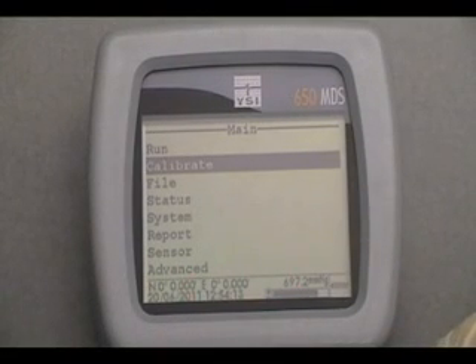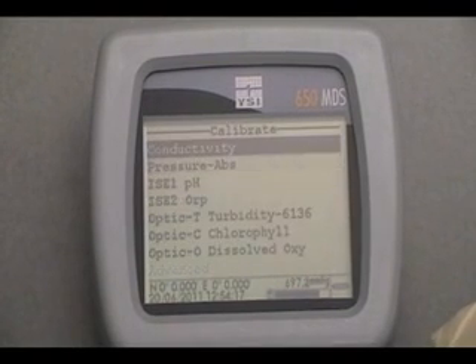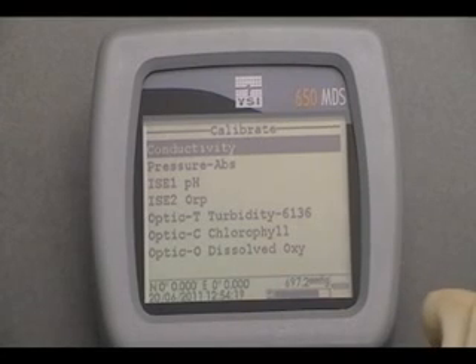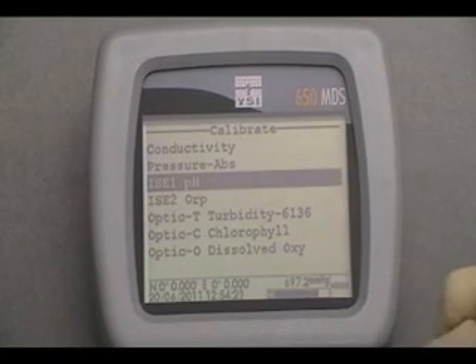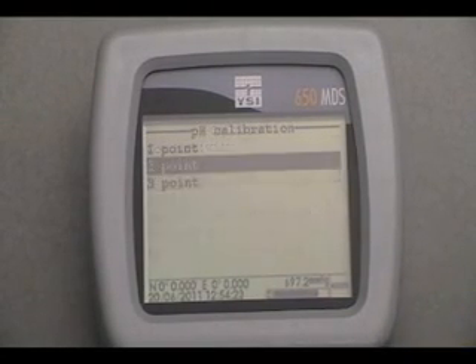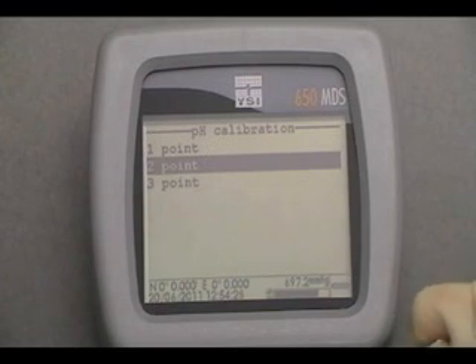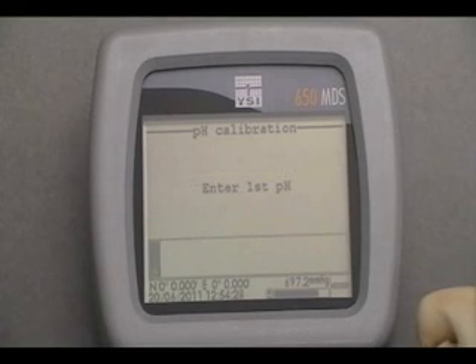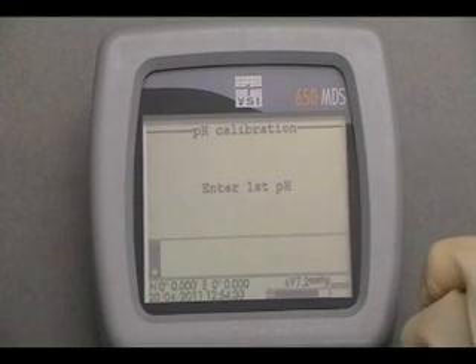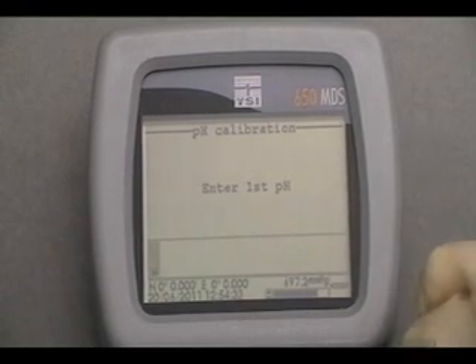Step 4. From the sonde menu, select Calibrate and press Enter. Step 5. Select ISE1 pH and press Enter. Step 6. Select 2-point, press Enter. Step 7. Input the value of the pH solution at your calibration temperature. You can find this on the table on the standard bottle. At the prompt, enter the value and press Enter.